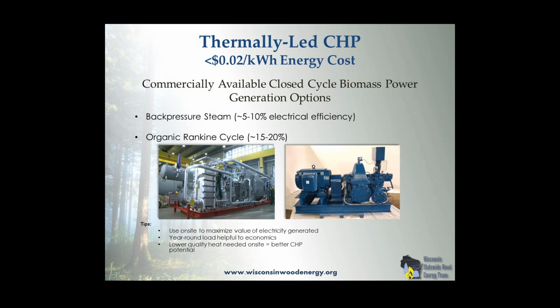5% condensate going through a 50% efficient turbine, and if you can deliver less than 50 psi steam to the system, you can typically get about 8 kilowatts per 1,000 pounds of steam from a system with moderate pressures. And when I say moderate pressures, in the 250 psi range. Very old technology, mature technology, very reliable technology. On the projects we've done, with 35 or so, maybe 37 installations, there are 5 to 7 back pressure steam systems.